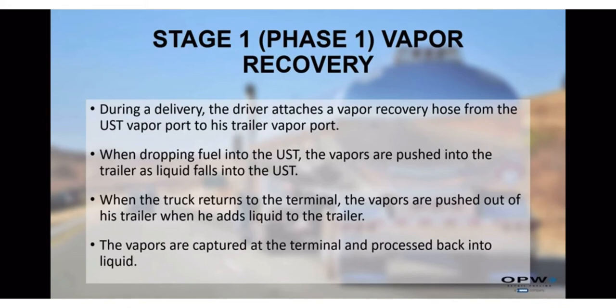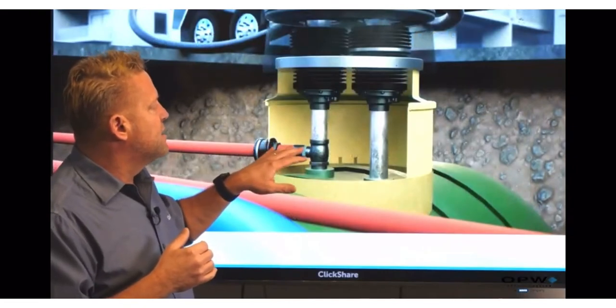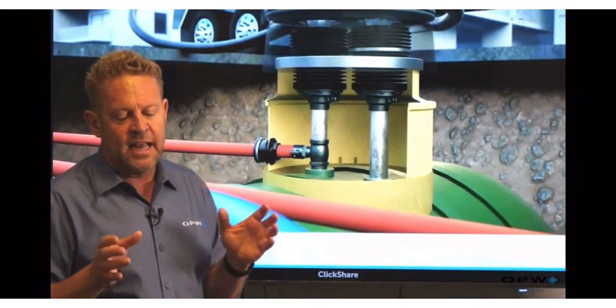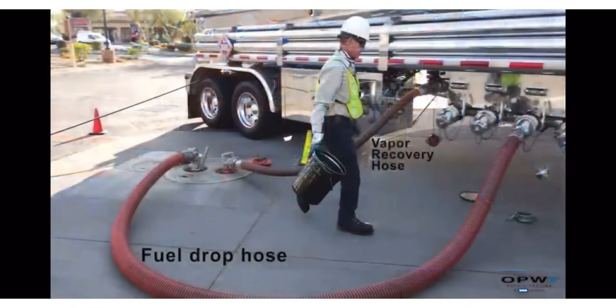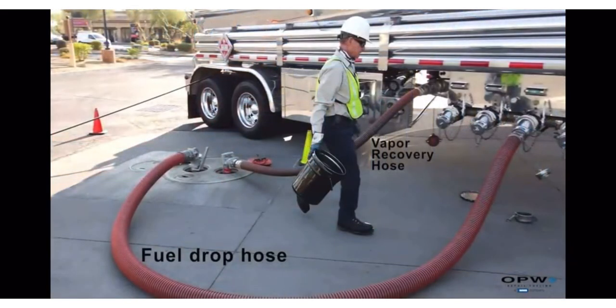This whole process of collecting vapors from the tank during a drop is what we call stage one vapor recovery. What I'm showing here is what we refer to as a two-point fill. One point we're dropping, and the second point we're actually collecting the vapor, so we have two different hoses.